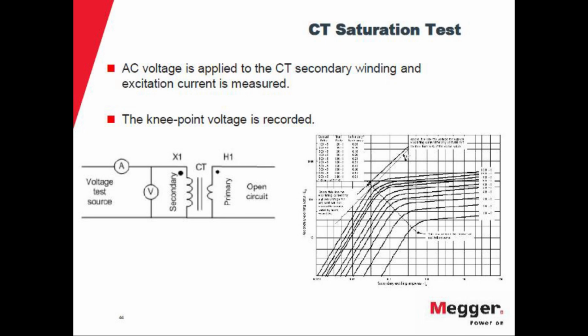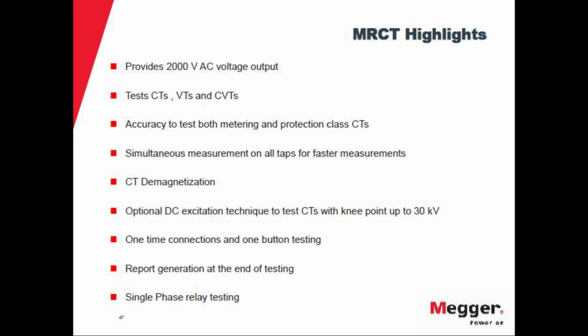So to be able to saturate those CTs, you would need a very big source. With a different technique that we developed, by using a DC signal, we can saturate CTs that have a knee point up to 30 kilovolts. These are very specific CTs, generation system CTs that will be able to withstand very high faults, and they have a very high saturation point. So with this instrument, you can test this type of CTs without any problem.